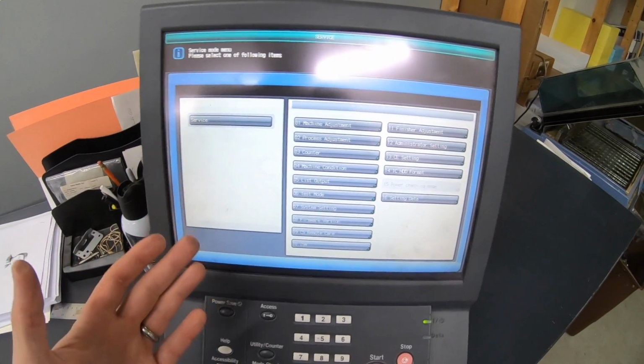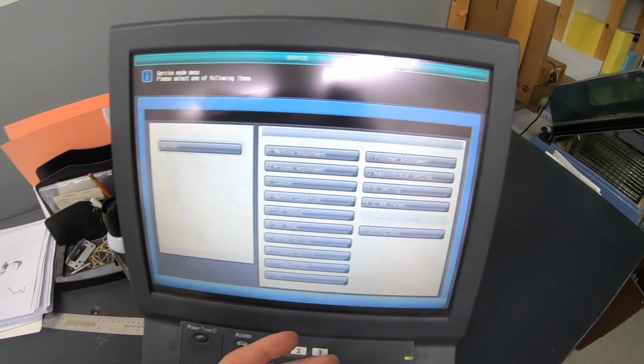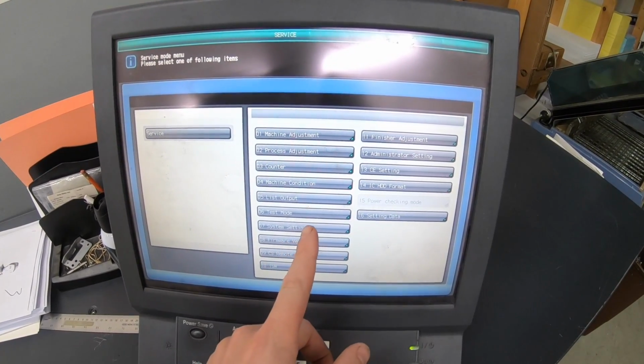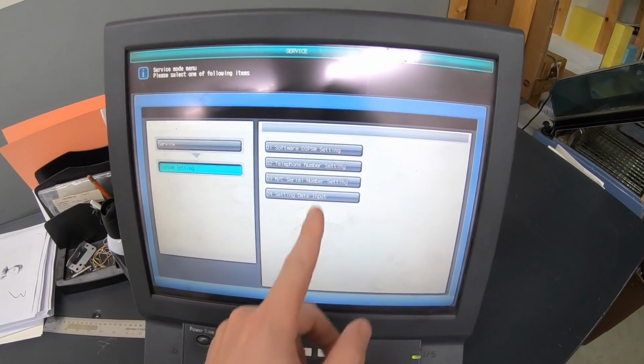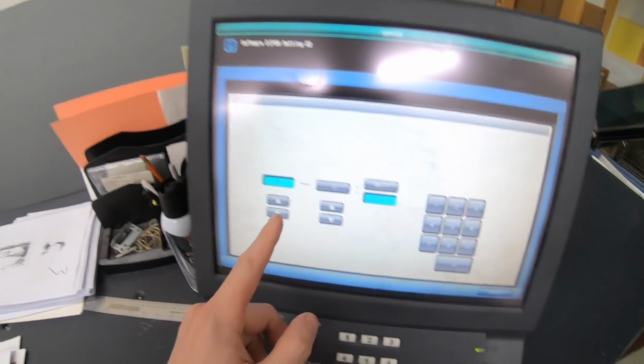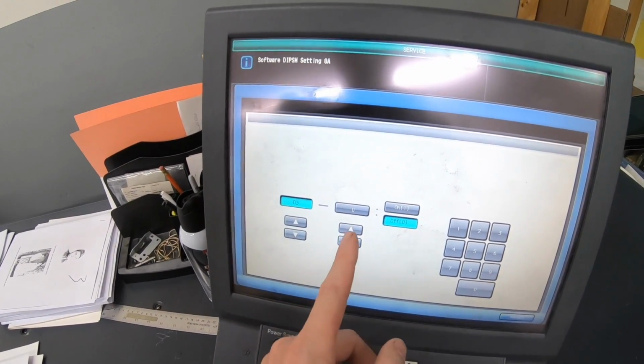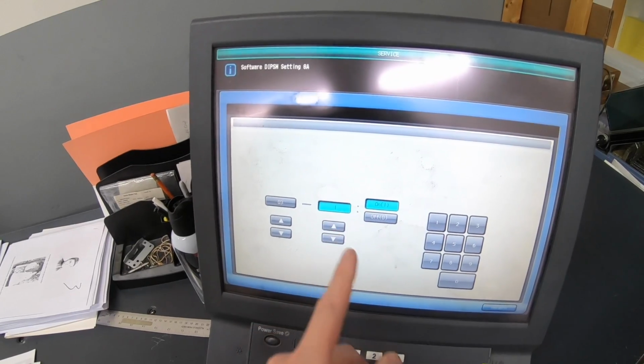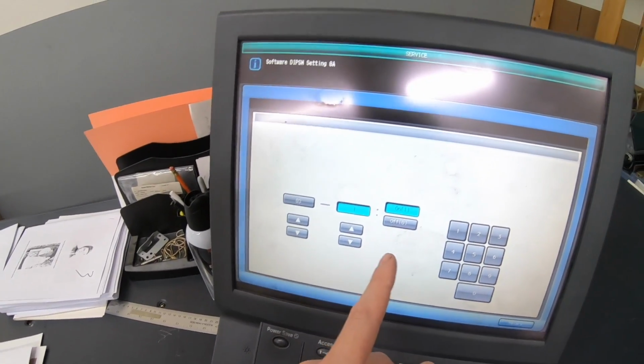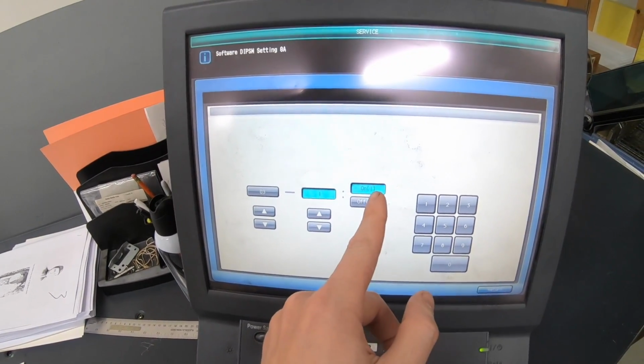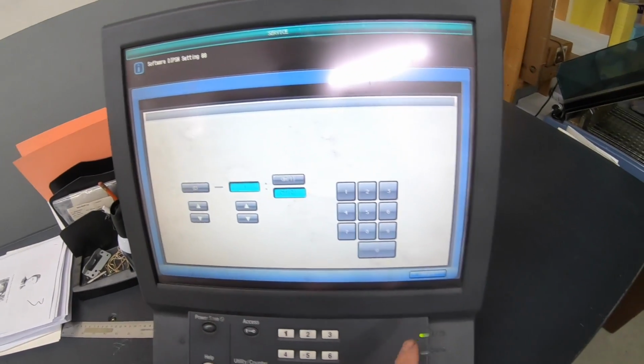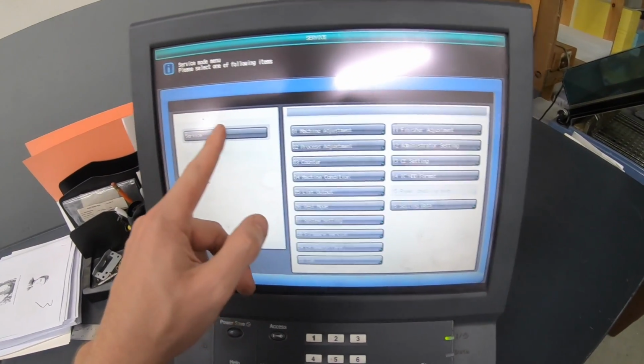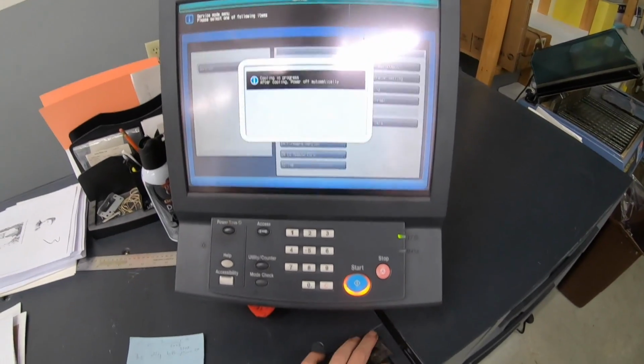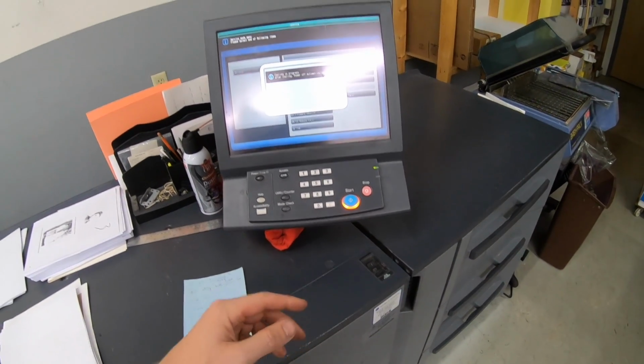Once you're in technician mode, it's simple. Go to system settings, then dip switch setting, then go to switch 1, which is on, and we want to turn it off. Put it to 0, hit return, then back out of this and turn it back off. Then when you boot up, it should be good.